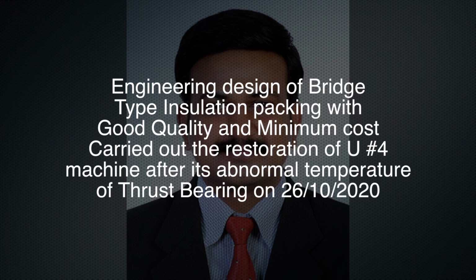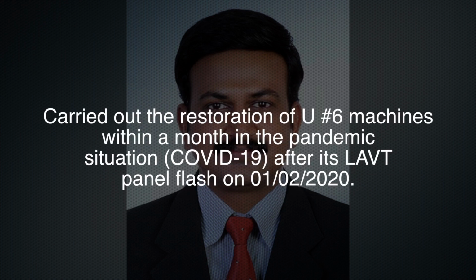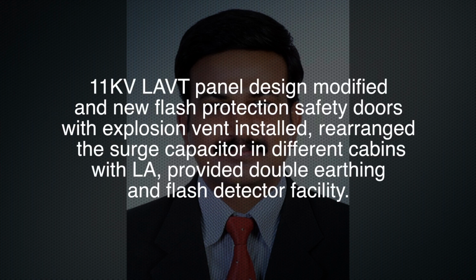He has also carried out restoration of Unit 4 machine after its abnormal temperature of thrust bearing on 26/10/2020. His works include carrying out restoration of Unit 6 machines within a month in the pandemic situation after its LAVT panel flash on 1/2/2020. 11 kV LAVT panel design was modified and new flash protection safety doors with explosion vent were installed, surge capacitors were rearranged in different cabins with LA, and double earthing and flash detector facility were provided.